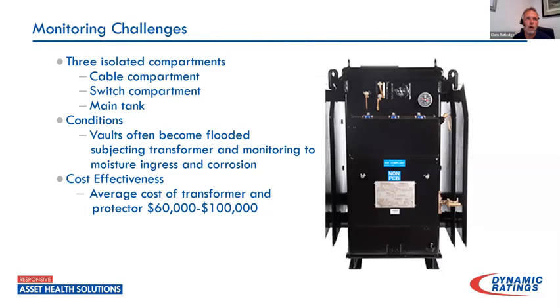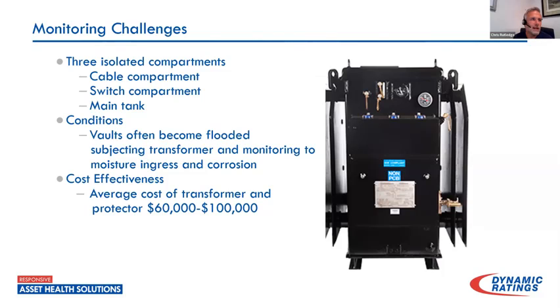I've seen customers injured, I've seen buildings catch fire, cars damaged, entire vaults ruined. The cost of the equipment is really secondary to what you're going to deal with if you have a failure. That goes across the board — even something as simple as a PT failure that would take out a bushing or a transformer. And especially when we get into breakers: if a breaker's not operating correctly, we're steadily robbing transformers of life, or if it totally locks up, we can fail in one event. So it's always that aftermath we have to look at.